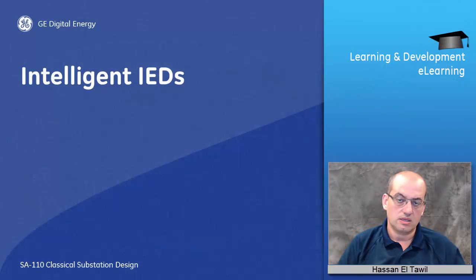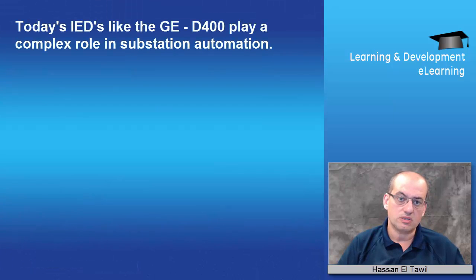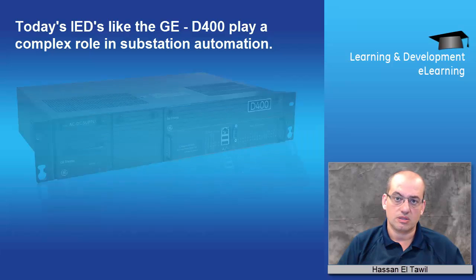The IEDs, or intelligent electronic devices, are part of the SCADA systems. They're microprocessor-based devices that collect, store, and transmit data. An IED can encompass or contain more than one logical IED, depending on the capability enabled in these IEDs.